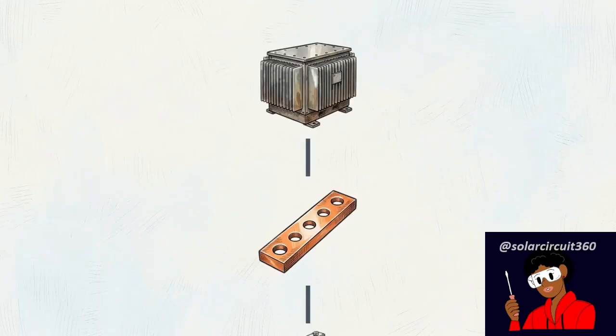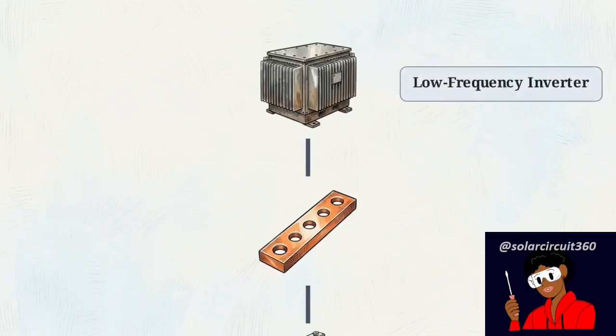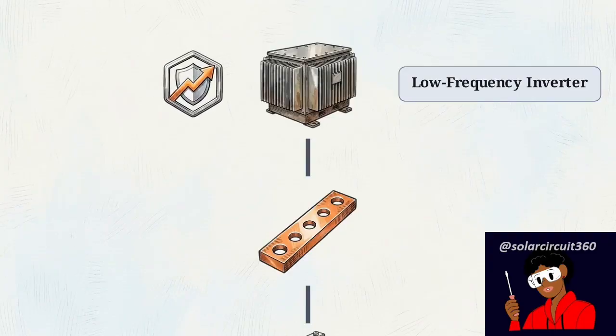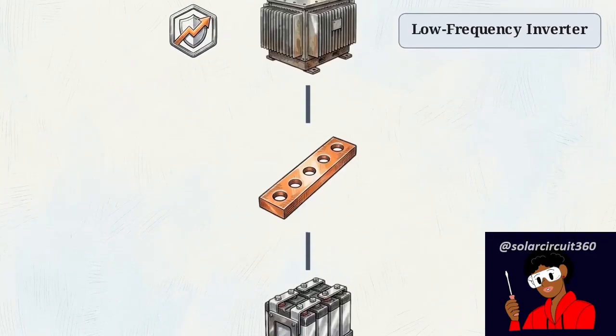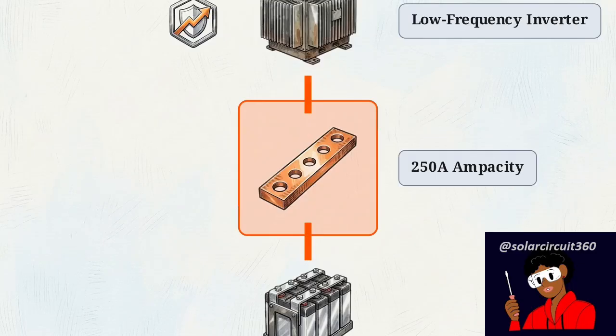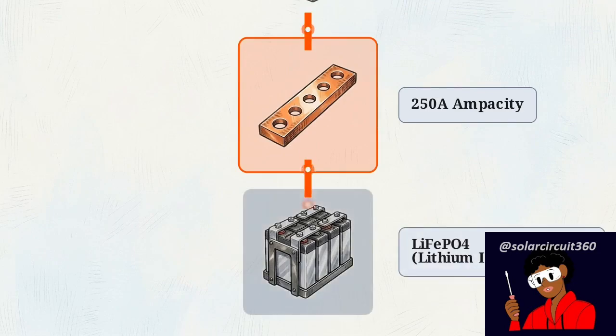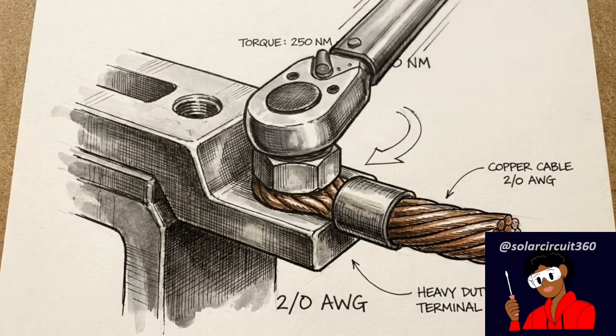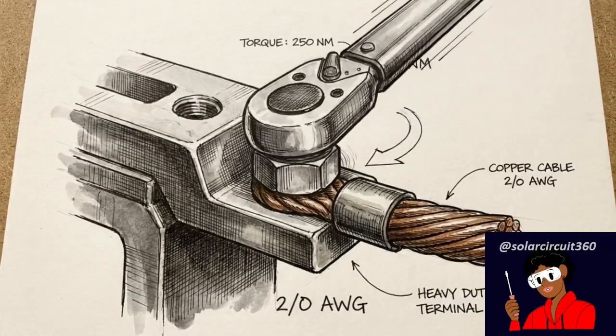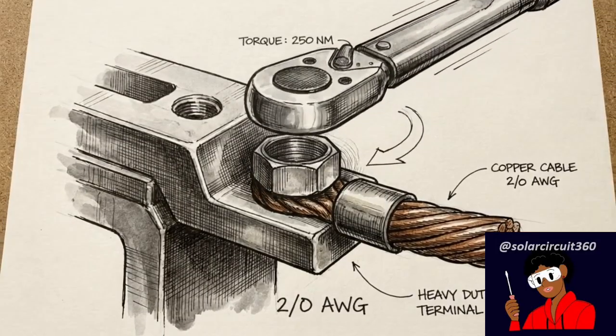This schematic outlines the architectural reality of a properly built commercial solar setup. On the alternating current side, the design requires a heavy, low-frequency inverter built with massive inductive surge margin to easily absorb multiple overlapping compressor starts. Tracing downward to the direct current side, you must specify oversized 250-amp bus bars, thick copper conductors, and high-capacity lithium iron phosphate batteries, capable of sustaining heavy, continuous discharge without voltage collapse. Every individual connection point in this heavy-gauge chain requires exact mechanical torque and industrial-grade physical compression to prevent thermal runaway.